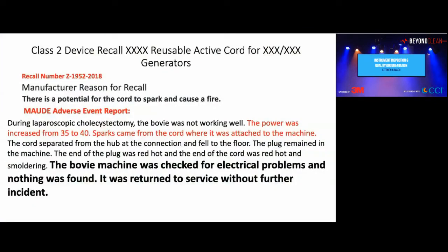The power is increased to 30, to 35, to 40. Sparks came from the cord where it was attached to the machine. The cord separated from the hub at the connection and fell to the floor. The plug remained in the machine. The end of the plug was red hot, and the end of the cord was red hot and smoldering. The Bovie machine was checked for electrical problems and nothing was found. It was returned to service without incident.